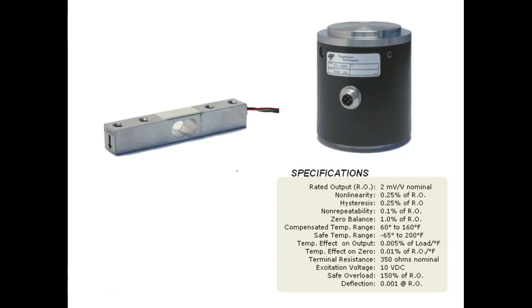I forgot what this was called. This was called a split beam, I think. So the load cell is actually mounted on here. This side would be mounted, and then your load would mount up here on that. What that would do is cause the metal to do what? To warp. And if it warps and you've got your load cell and strain gauge in there, it would change its position. And actually you can see where they put the load. This is the way it's rated, by the way. So your excitation voltage for this guy would be what? 10 volts DC. And then we have the output.